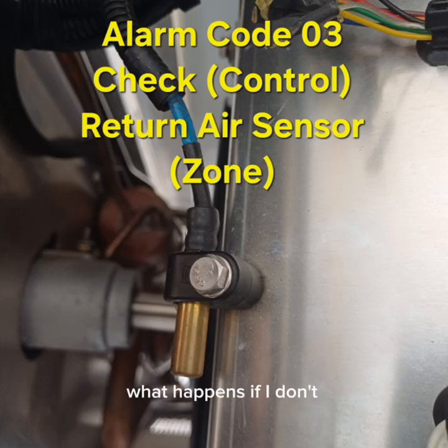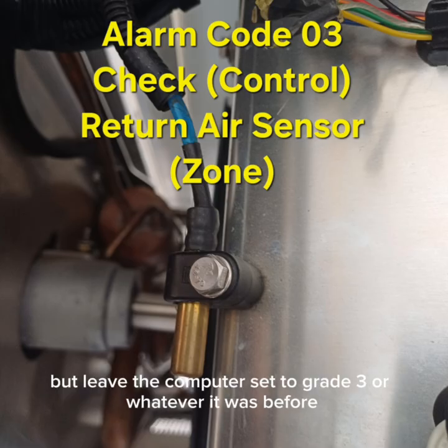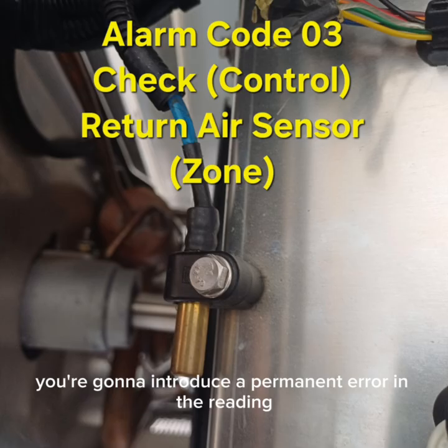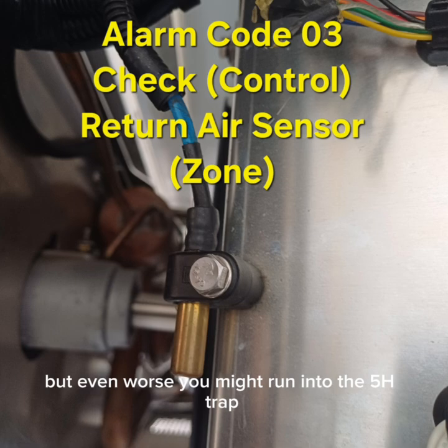What happens if I don't? What if I just plug in a grade 5 sensor but leave the computer set to grade 3 or whatever it was before? You're going to introduce a permanent error in the reading. The unit will think it's warmer or colder than it actually is. But even worse, you might run into the 5H trap. 5H trap. That sounds like a cryptic error message.